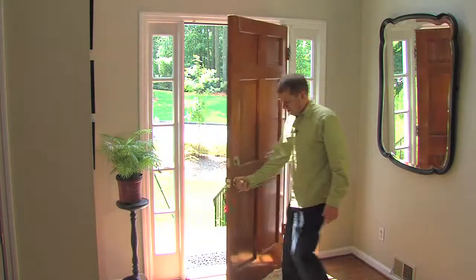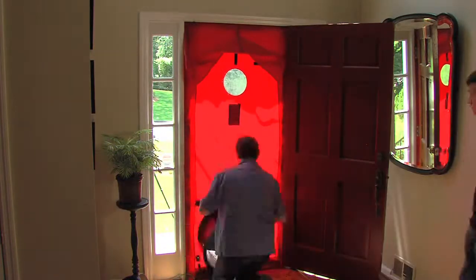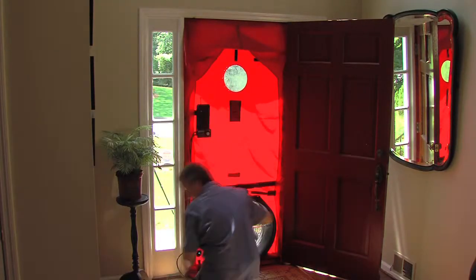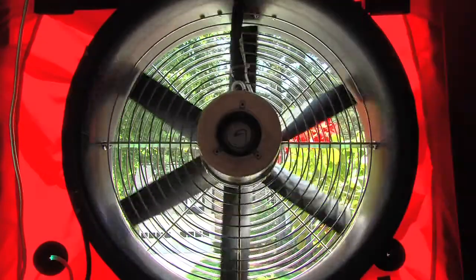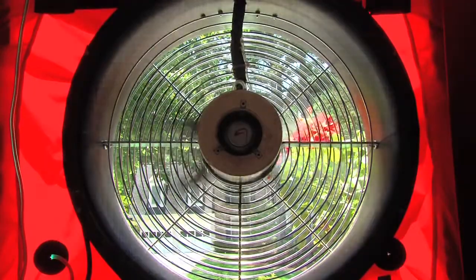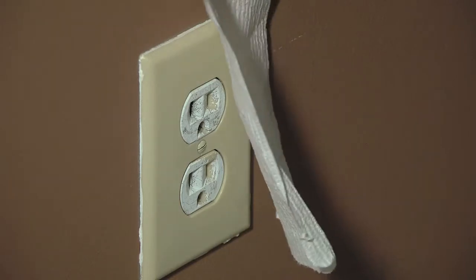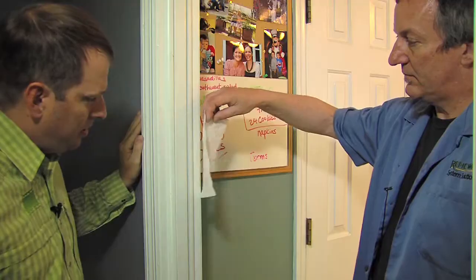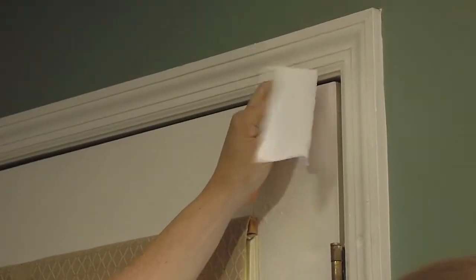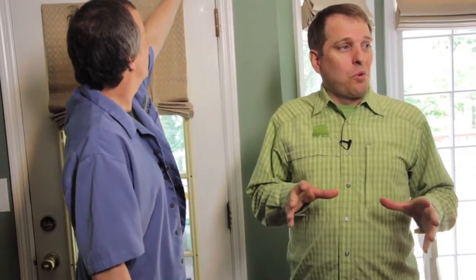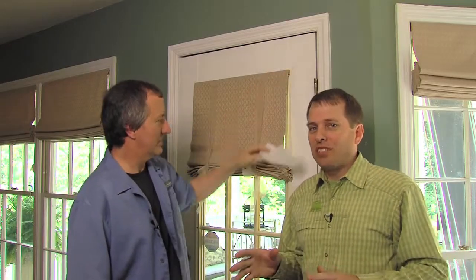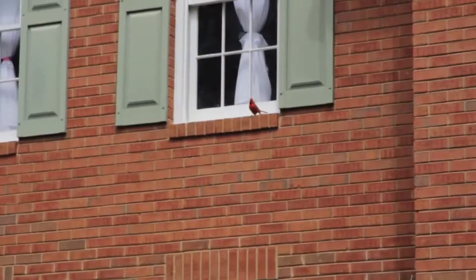Well, let's get the door set up and we can find some leaks. Let's go leak hunting. While a smoke stick is often used to find leaks, the method we used to indicate air infiltration was a couple of squares of toilet tissue. Wow. This one is just embarrassing. So with this area right here at my back door being a big problem, we're going to seal this up real quick with some tape, and then take a look at the readings and see how much this single problem is having an impact on the air exchanges here in the house.